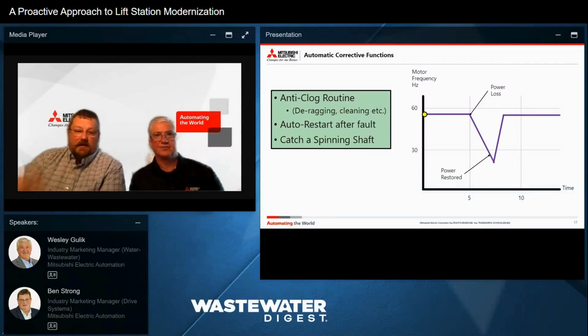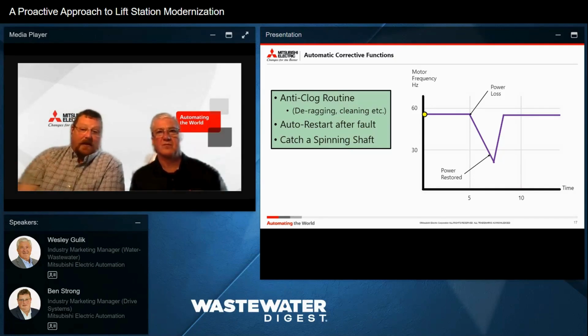What I'm showing here on the right side is how to catch a spinning shaft. So if I'm operating the pump and I lose power in the middle of operation, if I take these advanced functions and use them, I can catch the motor shaft before it slows down when power is restored and speed it back up. If I'm doing this across the line, I have to make sure that pump is stopped before I close those contactors again. Otherwise, I'll have a pump at speed, and I'll be trying to instantaneously bring it up to 60 hertz. It's not a good thing for your mechanical system.